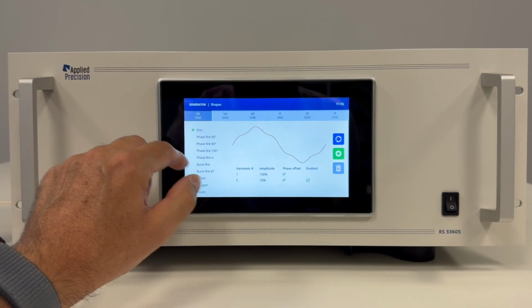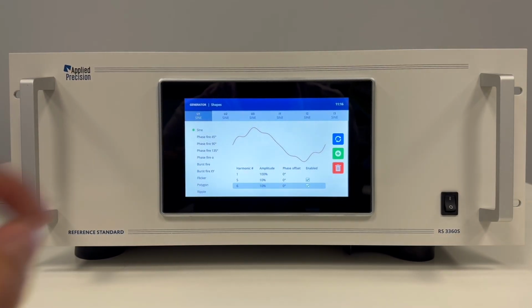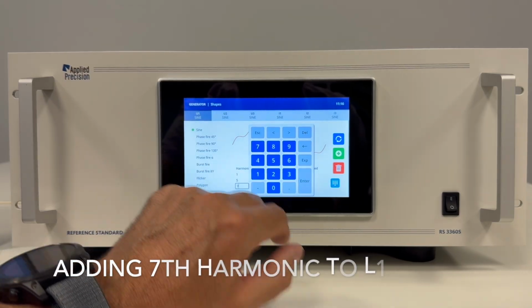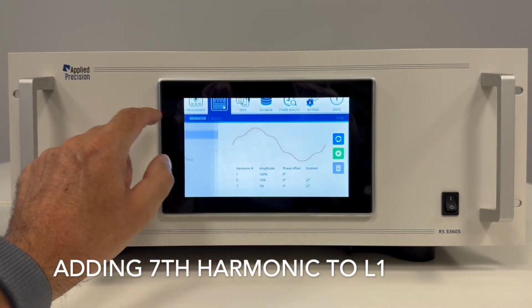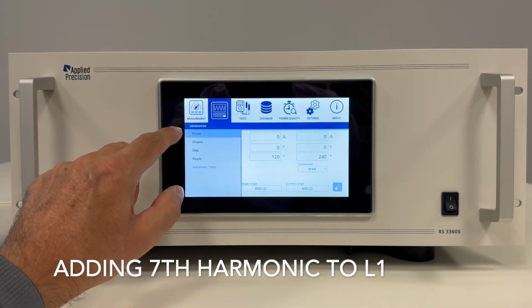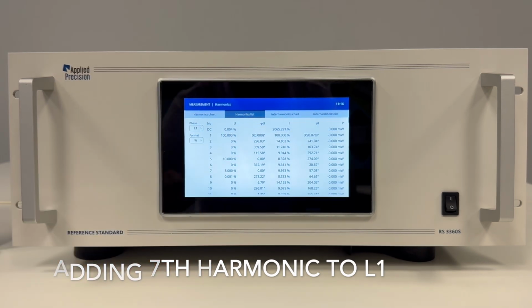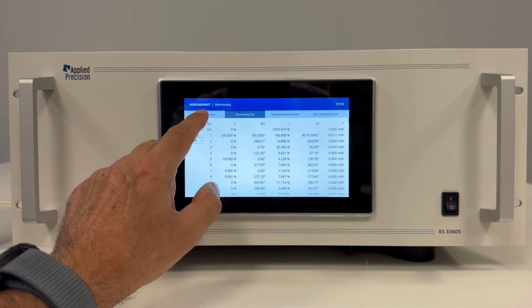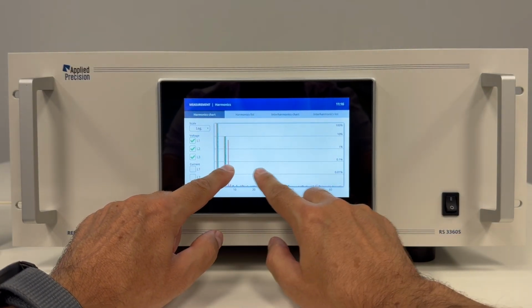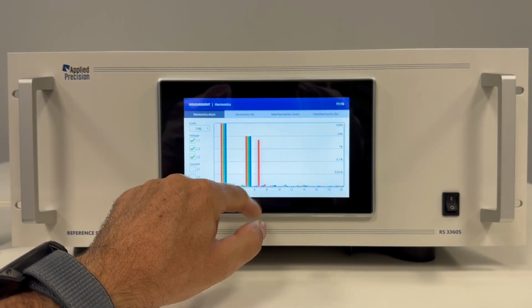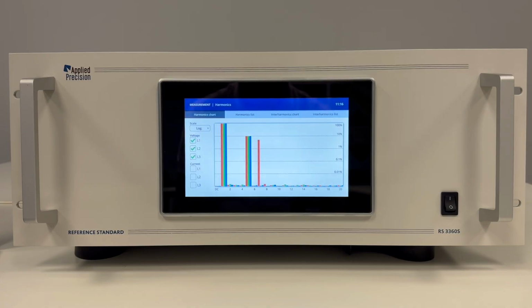We can go again to the generator, to the shapes, and for example for U1 we can even add another harmonic if required. For example, I can add the seventh harmonic with, okay, let's have it 5%. Yeah, we can see the signal. Let's jump again to generate, go to the measurement and the harmonics, and we will see that we have the 5% here, and in the graphical representation we can see it in the red color, which is dedicated to phase L1. So this is about high harmonics, how we can control and apply them with this device.